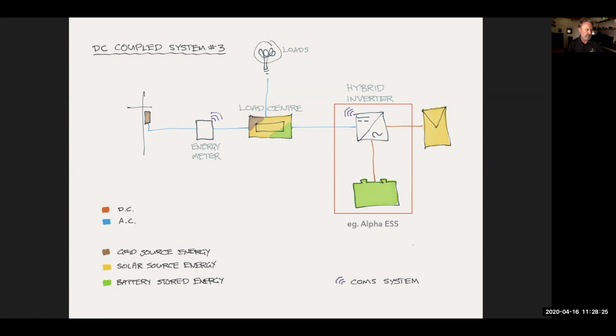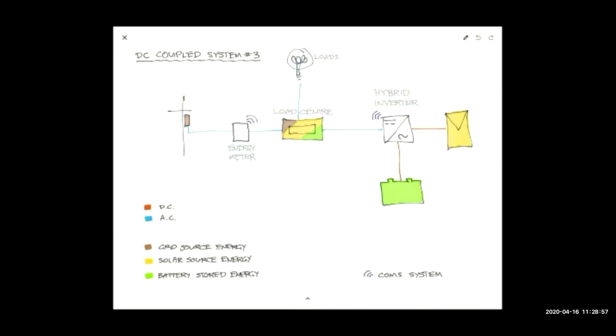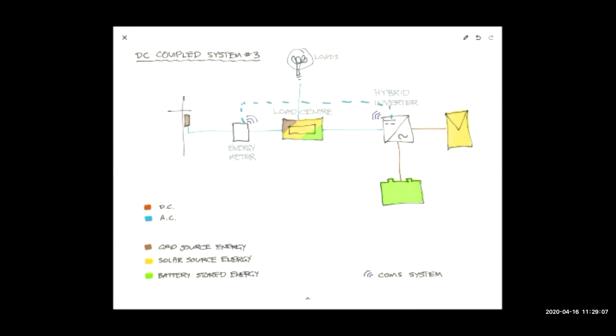Now, just to make that a little bit clearer, I wanted to illustrate that this requirement is still a consideration: you have a means of communicating between your energy meter, usually a comms cable, and the hybrid inverter. That's not a utility meter. That's often a small 1, 2, 3, 4, even 6 pole dedicated energy meter that comes with the equipment. So it's not normally a separate purchase, though sometimes it is in larger commercial systems. And that energy meter goes in, hopefully, the main switchboard. If you can't put it in a main switchboard, you only support the loads that are downstream of that meter. So it's pretty important when choosing a location for your hybrid system that you can get the energy meter upstream of all the loads you want to support. Because if it can't see the energy being consumed, that is, being imported from the grid, then it won't export power from its battery system to support that load.